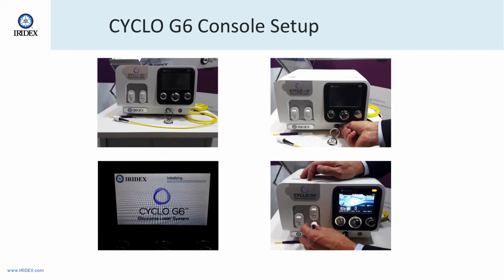Once you turn the key for the Cyclo G6 console on, you will see an initializing screen in which the laser will go through its self-check. Once this is complete, you can now plug in the laser aperture for the delivery device. The knob screws in, and once you start to tighten it down, you will see an orange to yellow glow around the probe, indicating that it has been seated properly. Make sure it is tight, but not too tight.